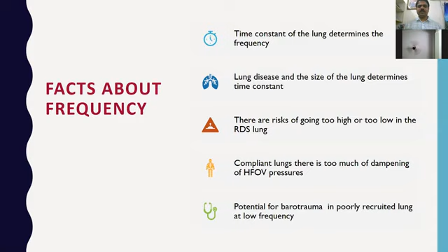So a stiff lung requires more frequency, and a smaller lung will require more frequency as compared to a larger lung. And you can't change it too much. Actually, there are risks of going too high or too low in the RDS lung. For example, the usual operating range of frequency in RDS is between 10 to 15. So you can't go beyond 15 or so.